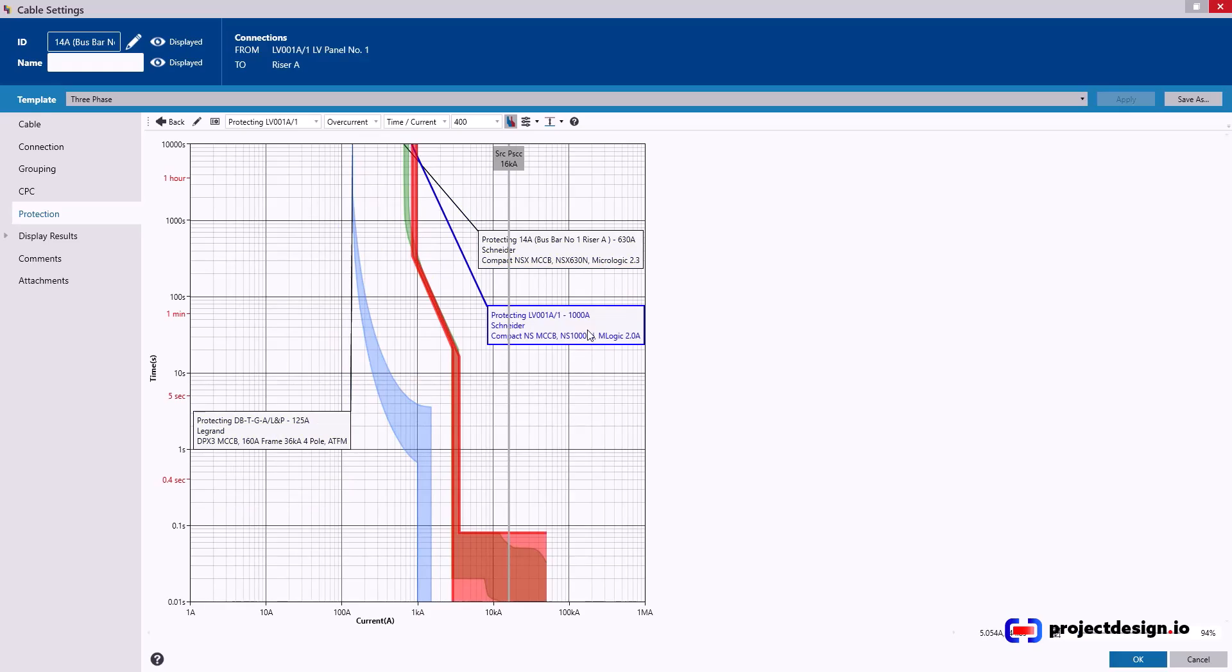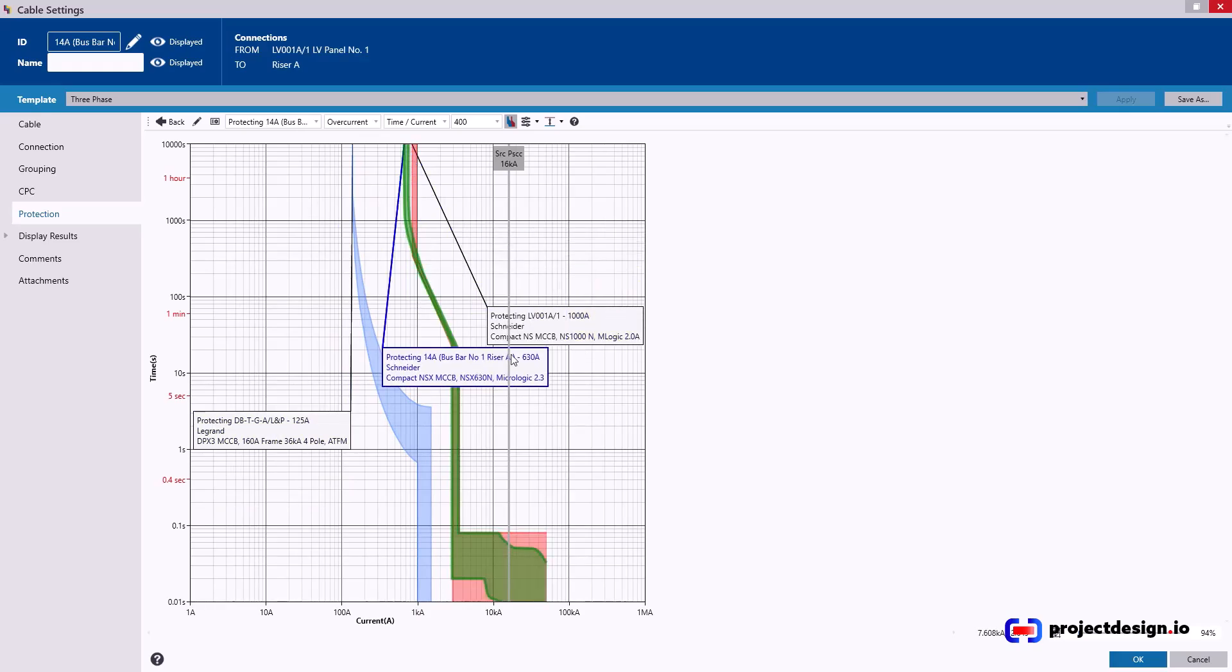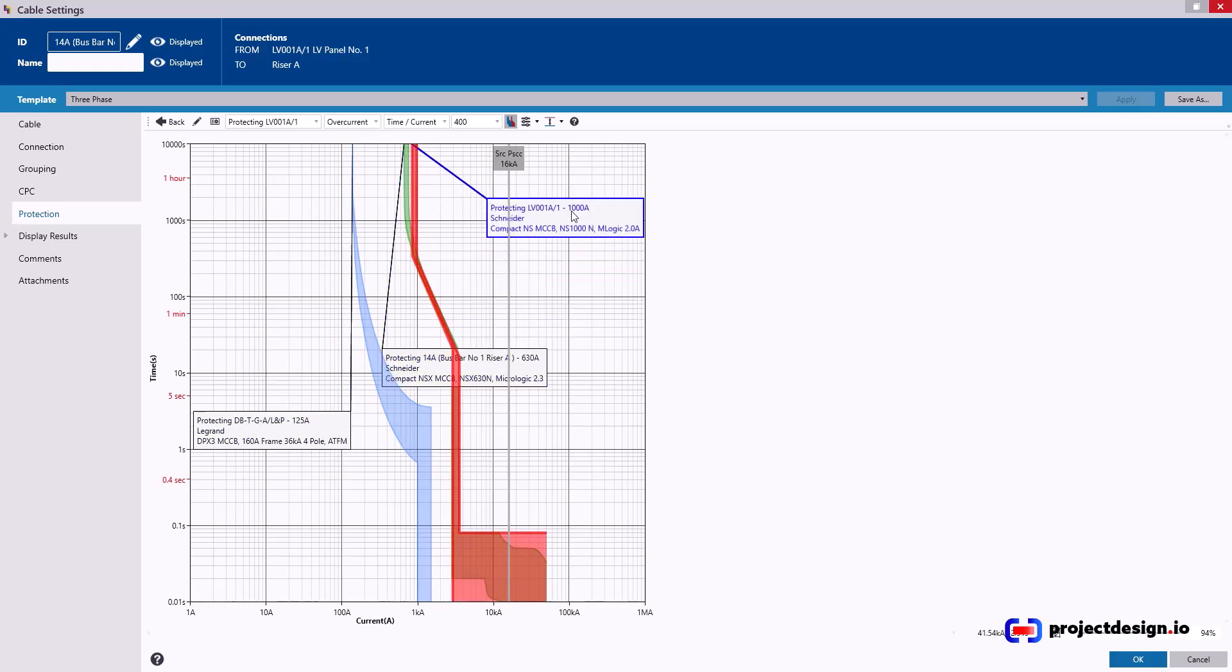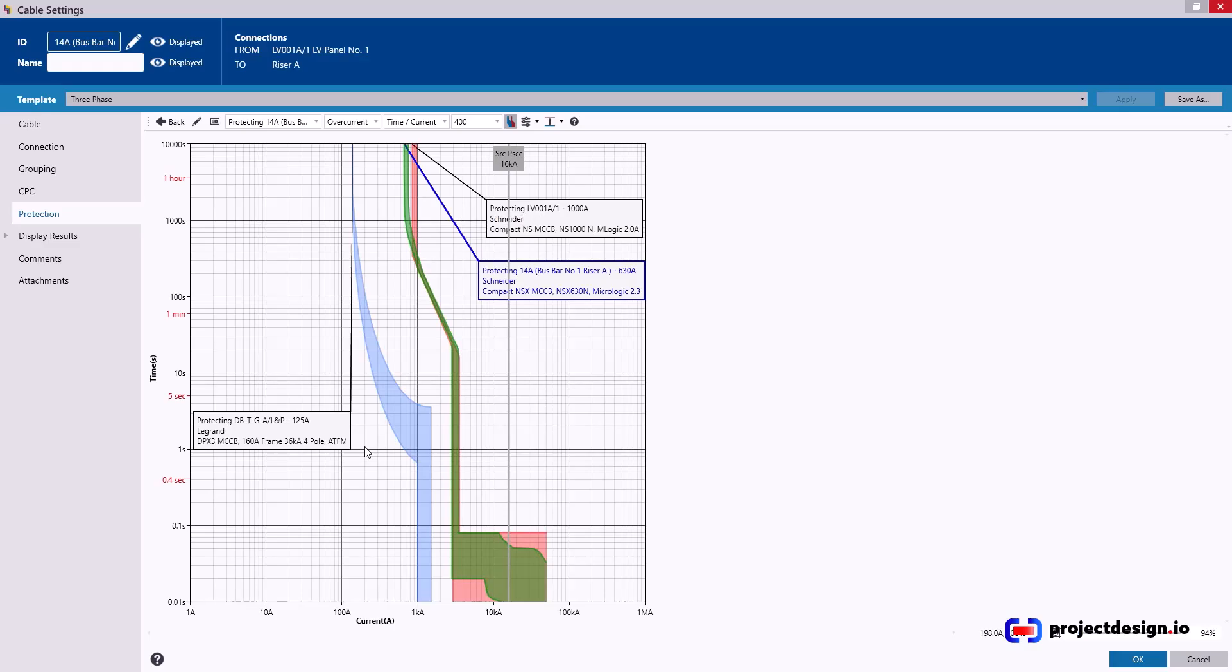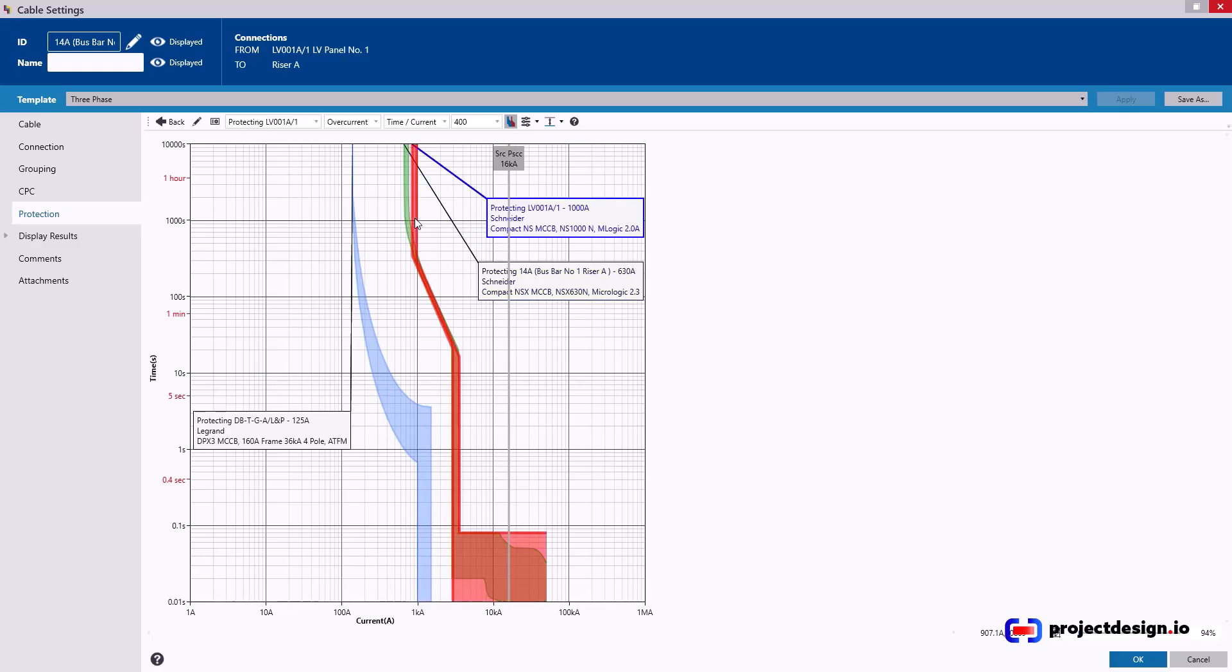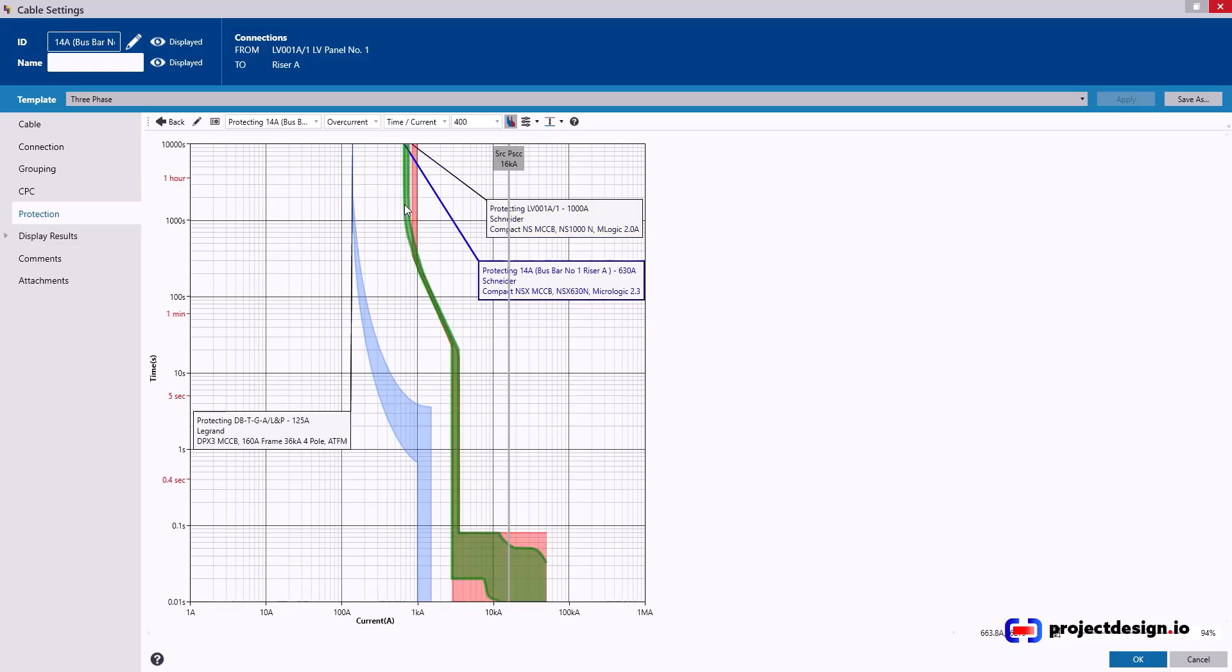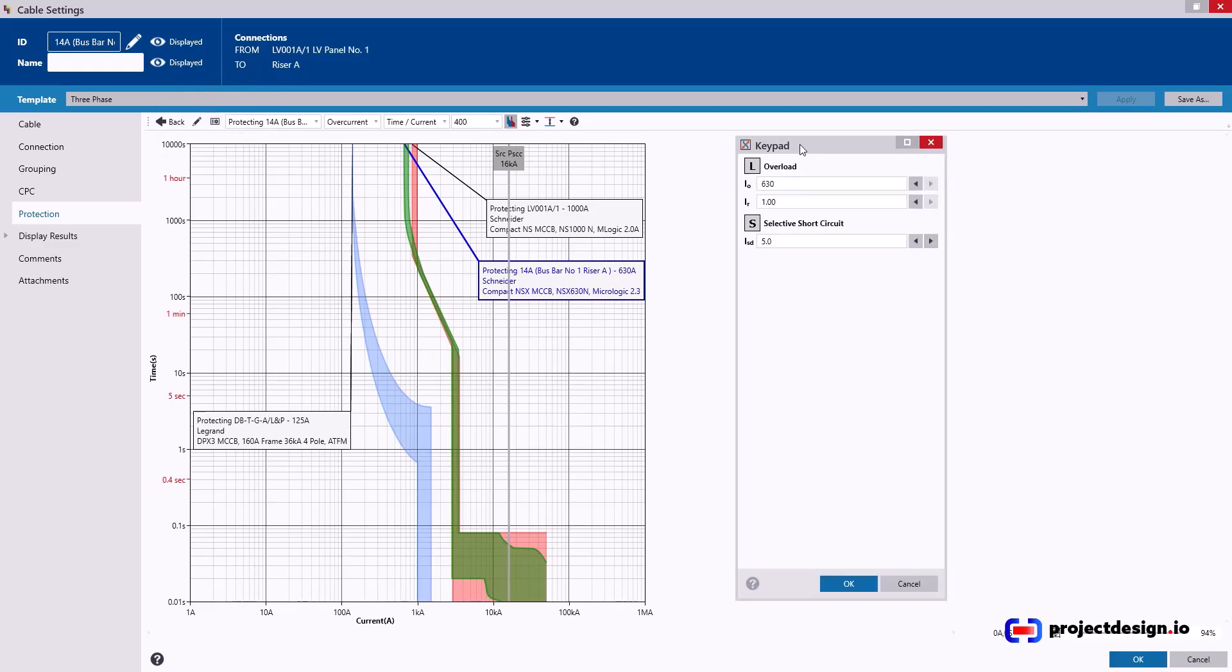Let's increase that size so you can see. Now I need to move those tags so I can see what's what. That's my tap-off. That's the red device, which is the upstream device. That's my green device. So you can obviously see that you can't achieve time current discrimination because they both overlap. What you can do is either push the green device forward to reduce its current capacity, or you can try to push the upstream device, the red device, backward, increasing its current capacity. Or you can actually do both.